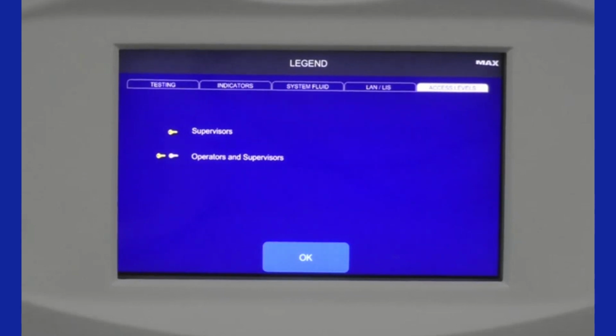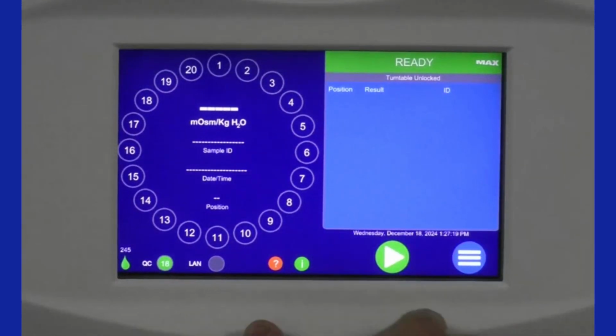Or if you're very particular about who you want doing what, then you can set up individual user profiles, and that's fine too. Pretty cool feature there as well. Okay, so here you'll also see the 20 position turntable on the left. You have your units there in the middle, milliosmoles per kilogram of water. That's where your result will pop up of the current sample being tested. And then you'll have a result log on the right side where your results populate until you run out of room there. But remember, we do store up to 1,000 results at any one time.